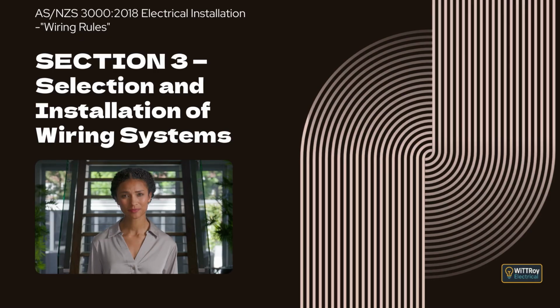Clause 3.12.5 Aerial conductor supports. This clause states that supports used for aerial conductors must be insulators or purpose-designed fittings that are suitable for the type of conductor being supported. It also explains that pin-type insulators must not be used where the strain on the conductor could cause it to lift or separate from the insulator, as this would create a safety risk.